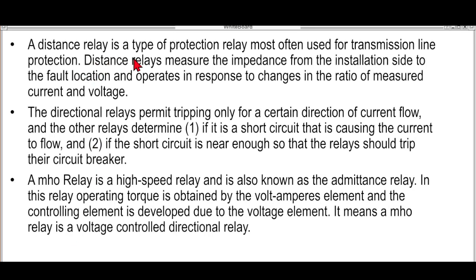Our distance relay is a relay used for transmission line protection. It measures the impedance of our transmission line. The directional relay will trip depending on the current flow. If a short circuit is causing the current flow, the relay should trip its circuit breaker.